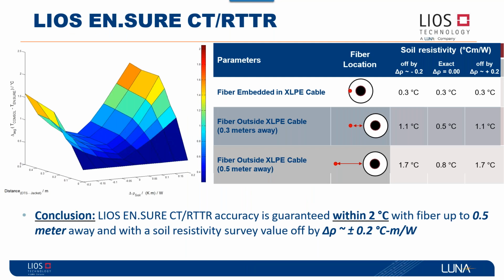We'll talk a little bit about LIOS RTTR, what makes us special, what makes us different from others. One of the main features really is the FEM, finite element modeling, approach. What we can do with that now, for special, challenging projects where you have a congested duct bank as represented, is use the fiber optic that's embedded in the power cable, or the fiber optic that's away from the power cable in an adjacent conduit. You can also go further out, about half a meter, guaranteeing an accuracy, as we showed here, of 0.5 degrees Celsius, plus or minus 1 degree Celsius, up to 0.5 meter.